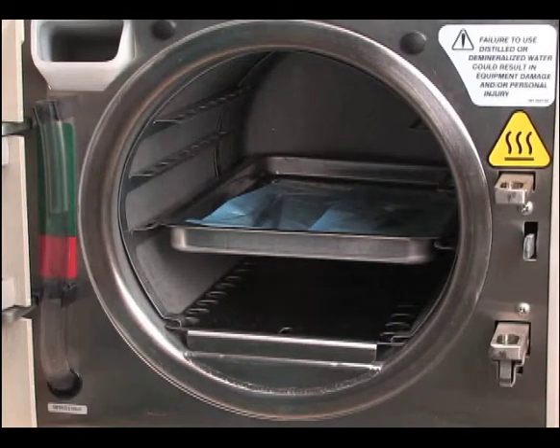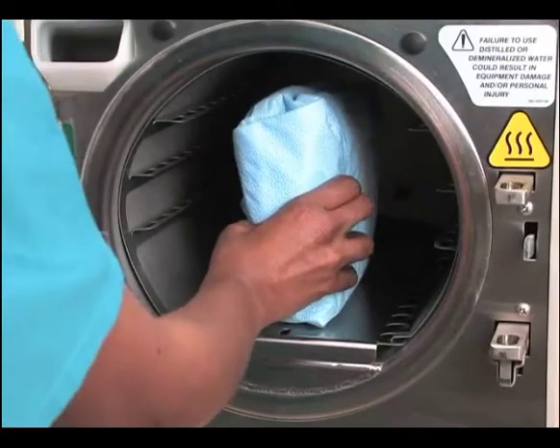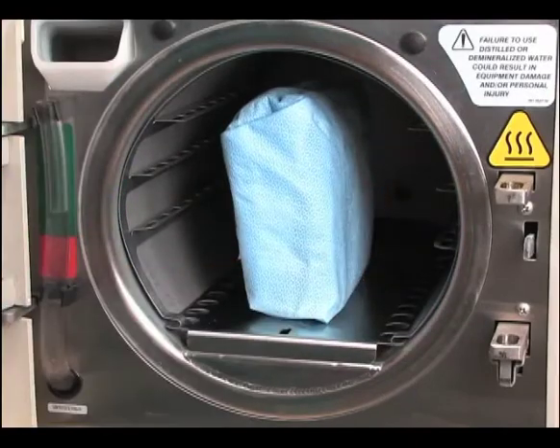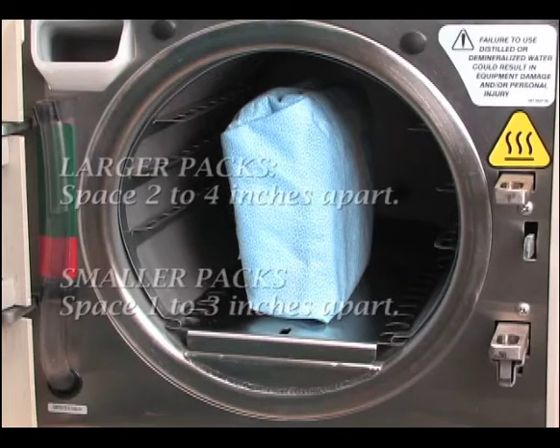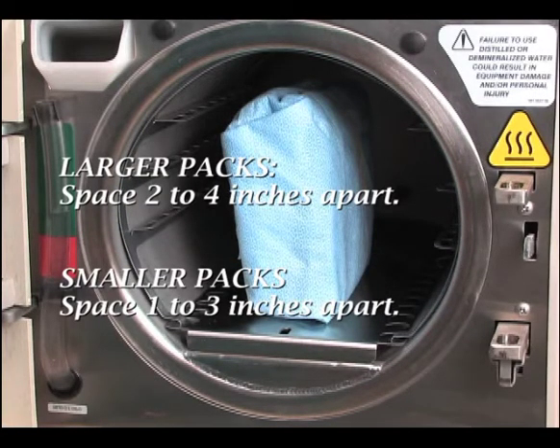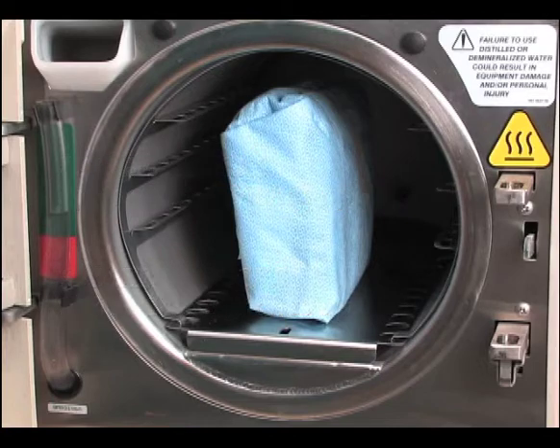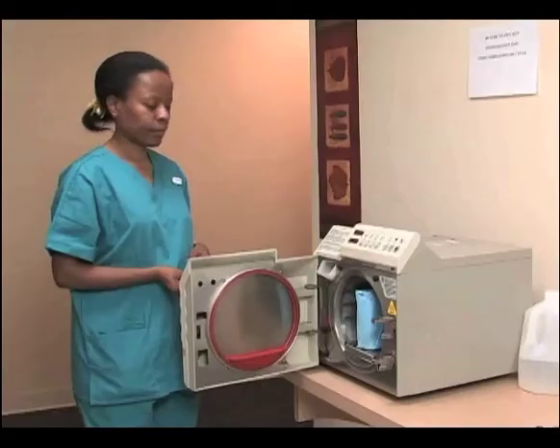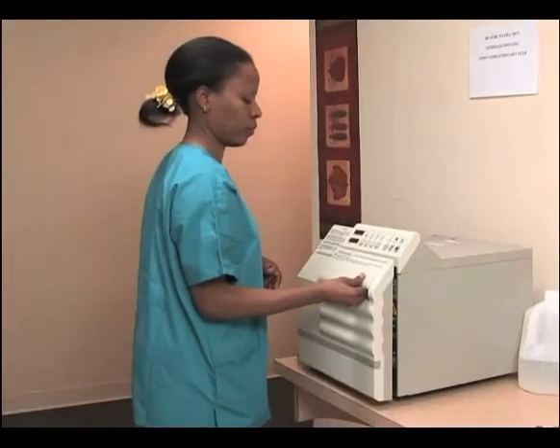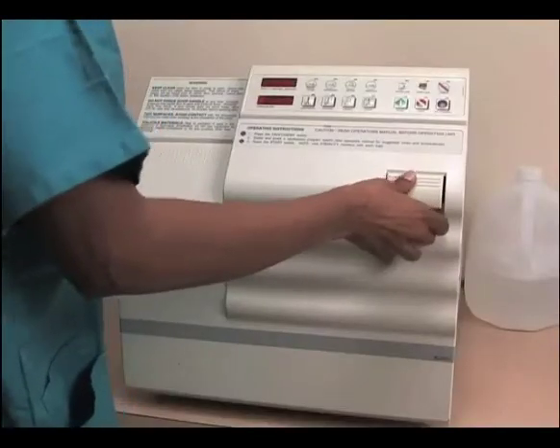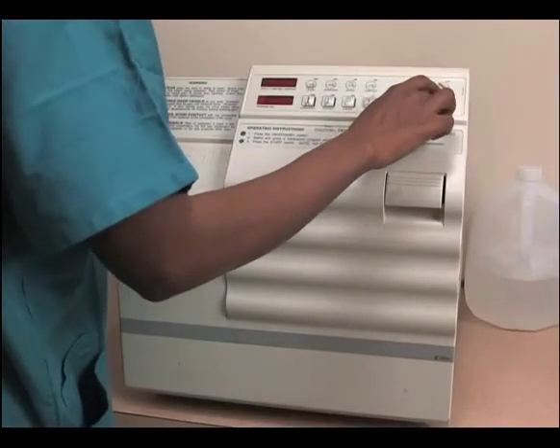Lids should be removed from containers before autoclaving. Dressing packs should be arranged in a vertical position to allow the steam to penetrate each layer. Larger packs should be spaced 2 to 4 inches apart, smaller packs 1 to 3 inches apart. Do not allow any of the packs to touch the surface of the autoclave chamber. Once the autoclave has been loaded, close and latch the door according to manufacturer's instructions. Turn on the autoclave.